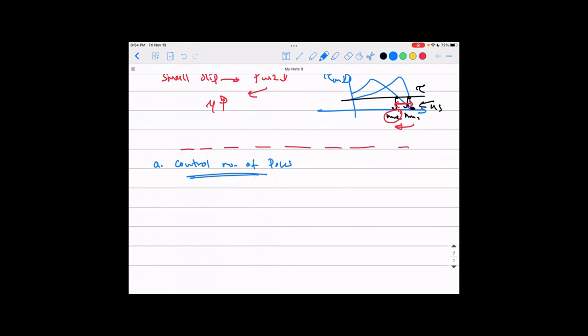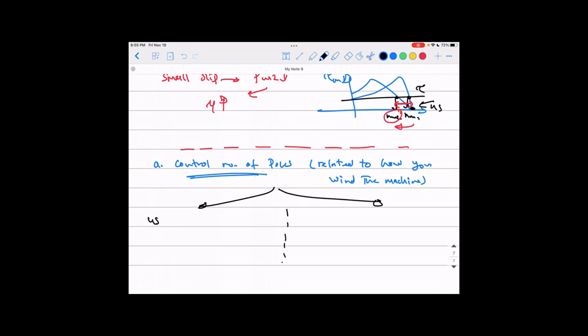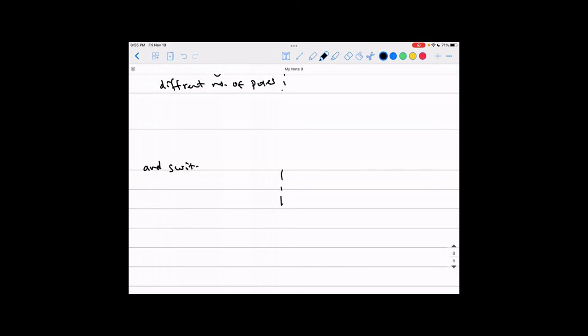To change the number of poles you have two approaches. The first one is using two separate sets of windings with different numbers of poles, and switching between them. That means on the same stator you have two different winding sets on top of each other in the same slots — one set with, say, two poles and another with four poles.